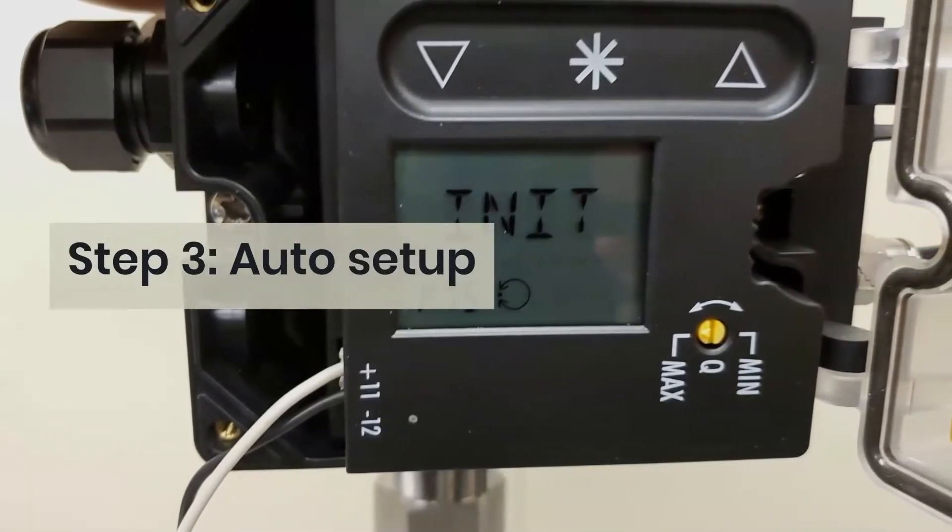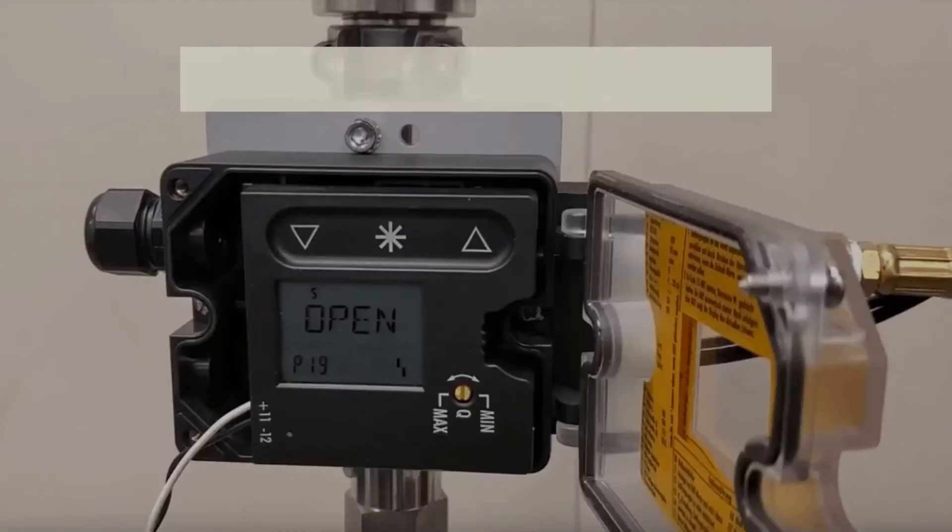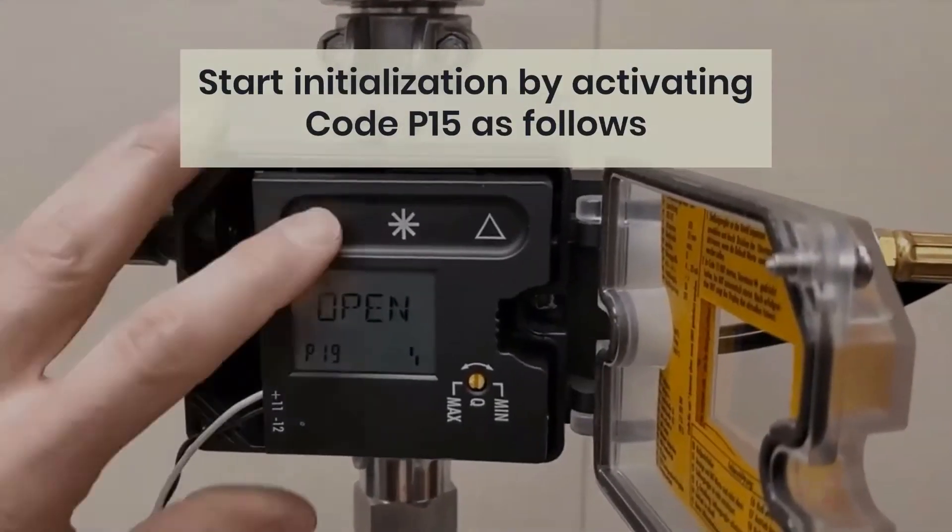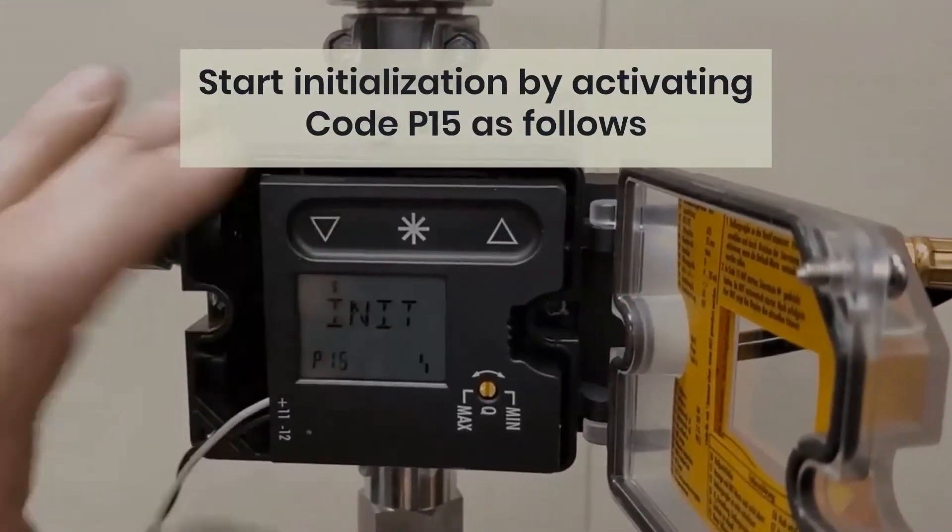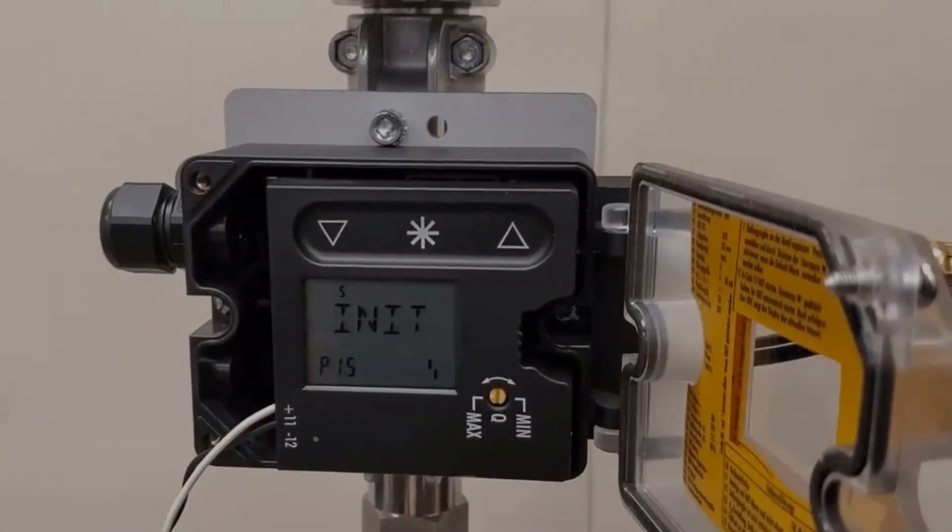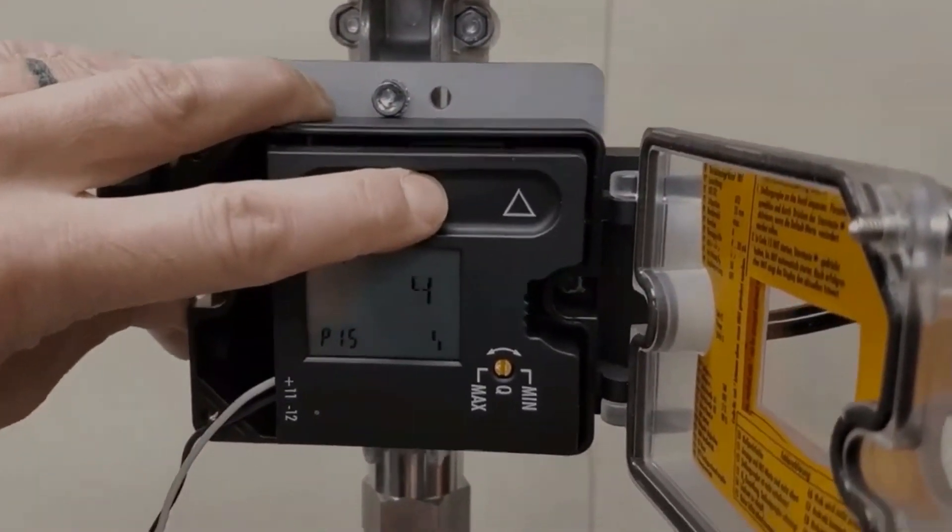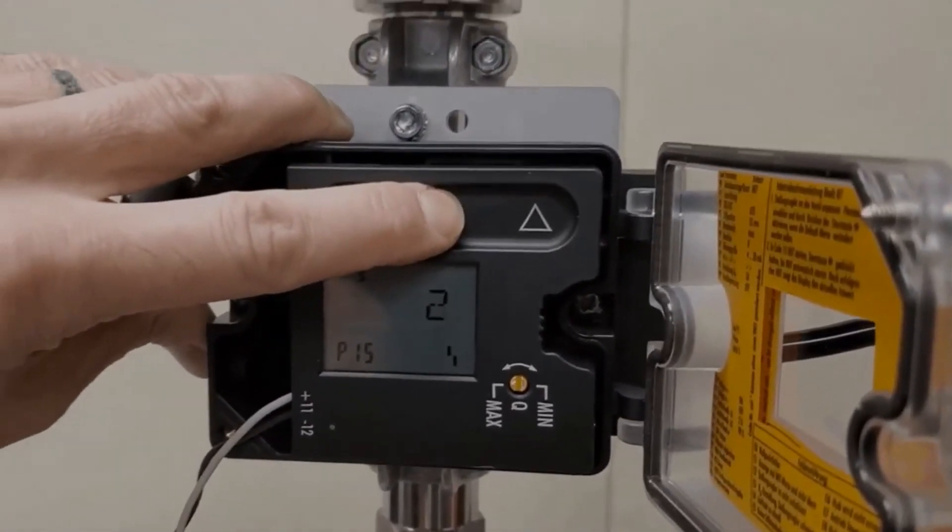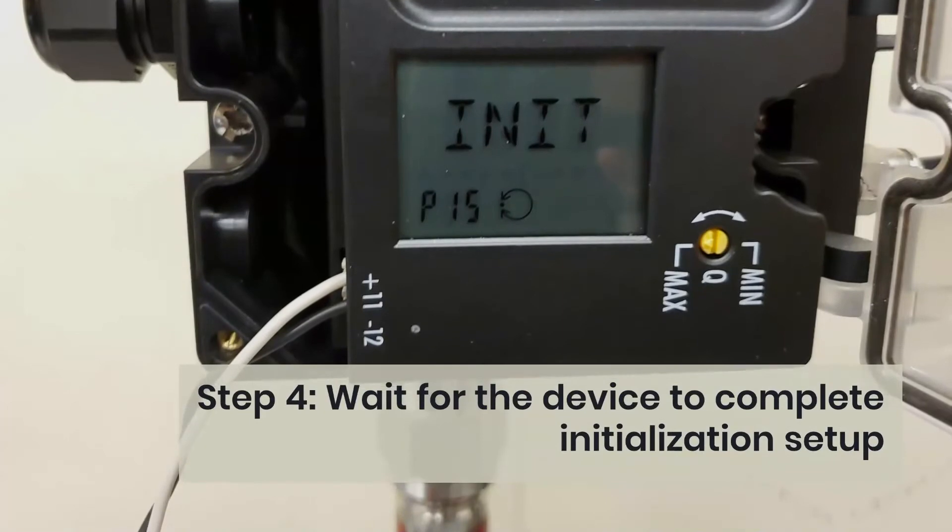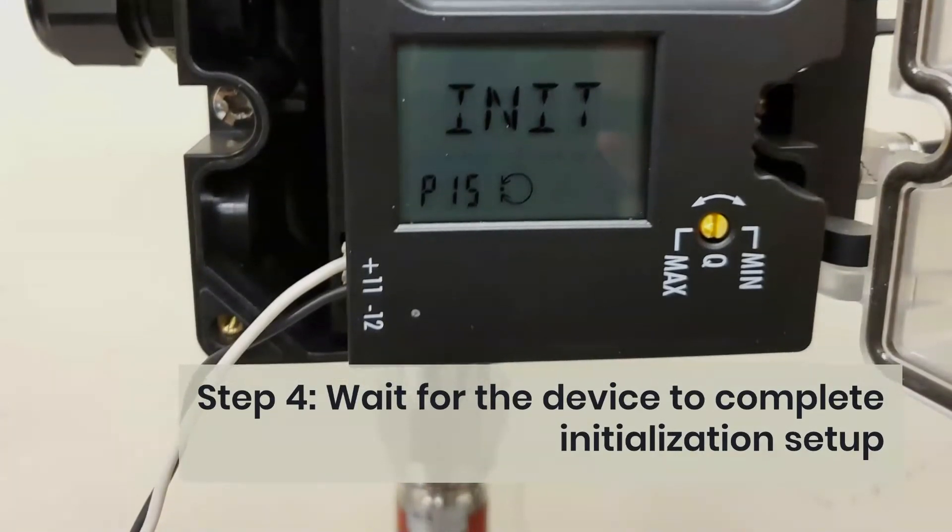Step 3: Auto Setup. Start initialization by activating code P15 as follows. Press the down or up arrow to select code P15. Press and hold the star symbol for 6 seconds. 654321 will count down on the display. Step 4: Wait for the device to complete initialization setup.